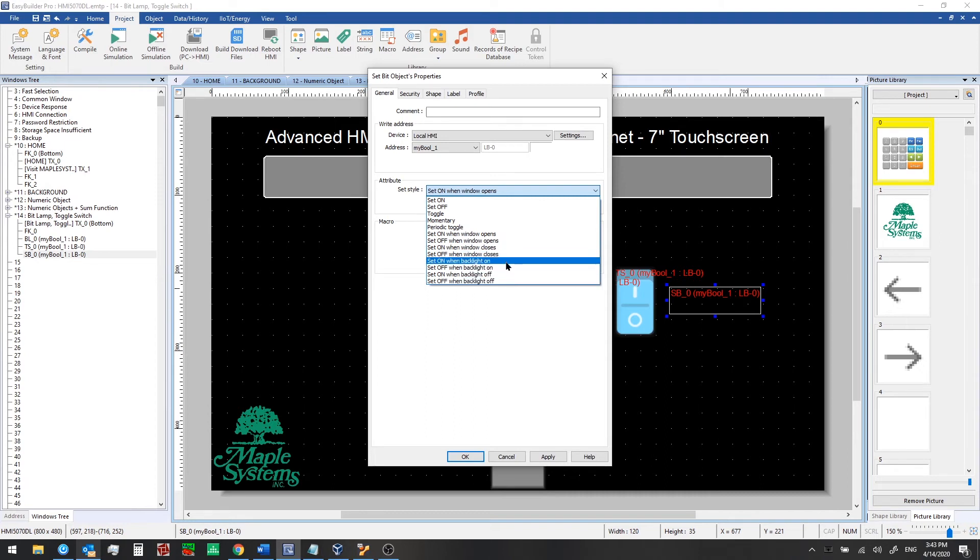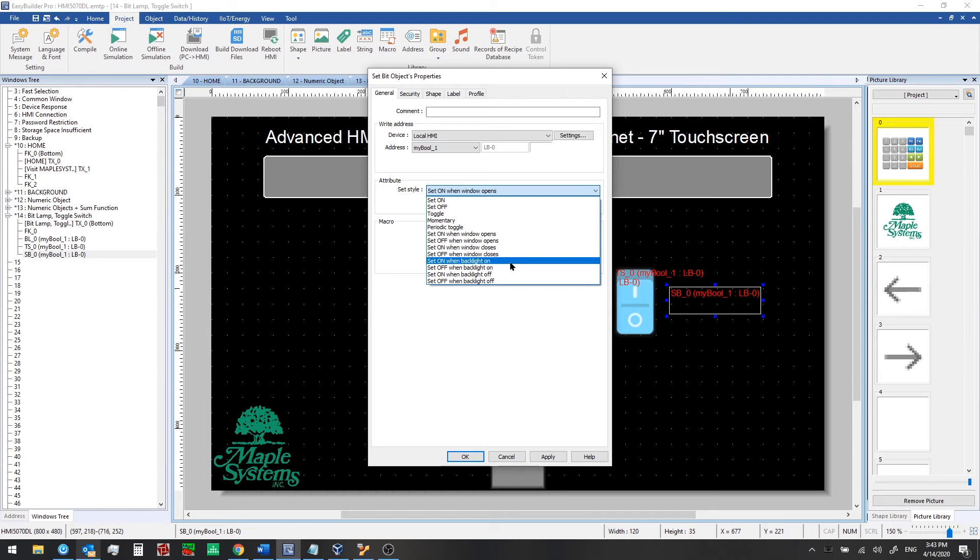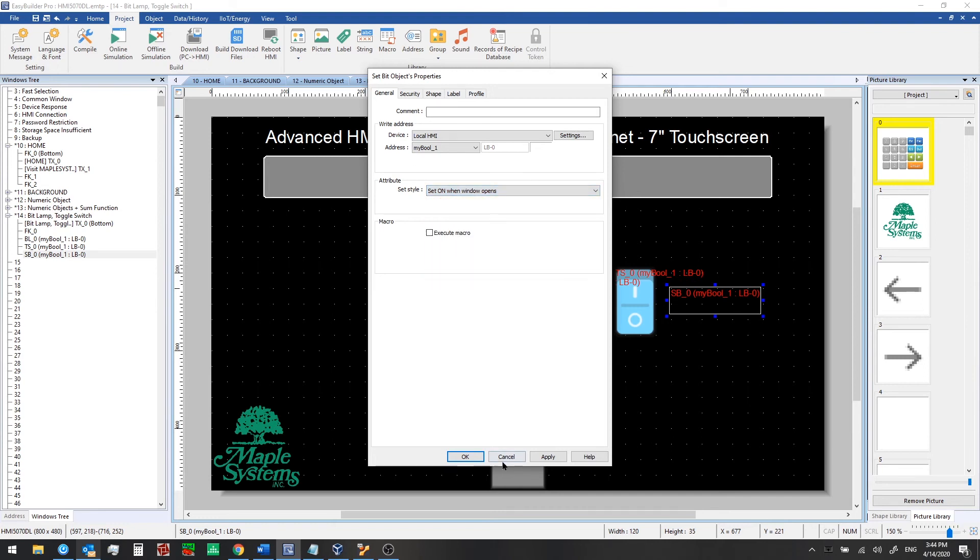And then the backlight. We'll take a look at this. So the backlight can be set to turn off after a certain period of time. Basically the display goes to sleep. So if you wanted to set on a bit or set off a bit when the backlight comes on, as in after the HMI has been asleep for a while, operator presses on the screen, set on a bit for some reason or set off a bit, we can do that. And same thing when backlight goes off. We can set a bit on and off. So when the display goes to sleep, we can perform this action if you wanted to do that.